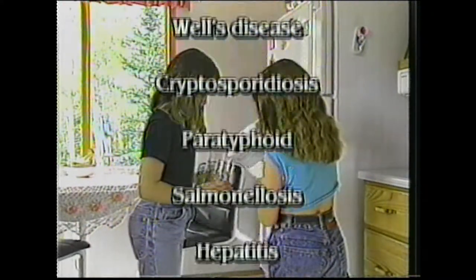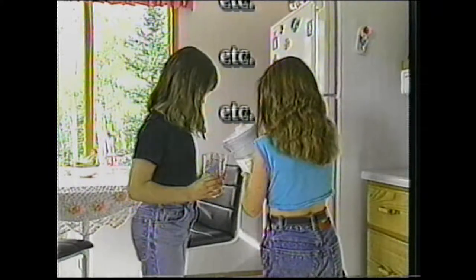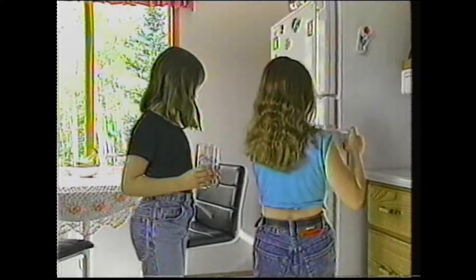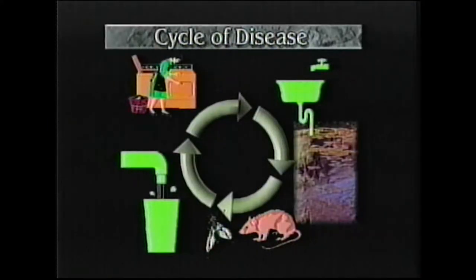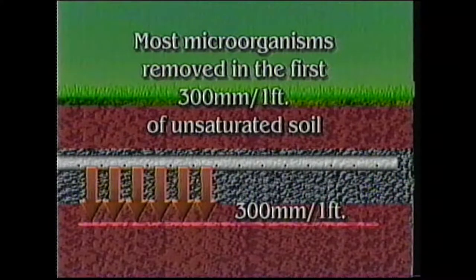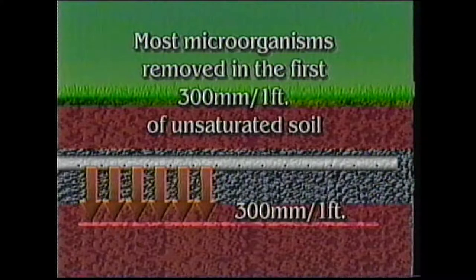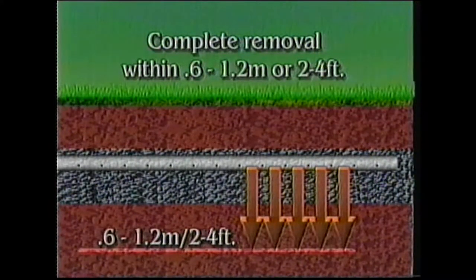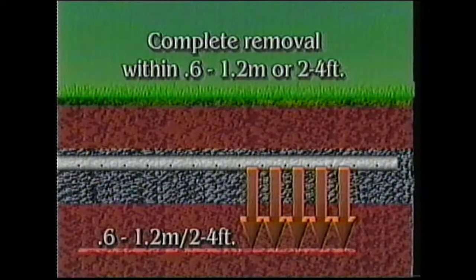The list is exhaustive and reads like a who's who of epidemics. Risks to human health arise through direct and indirect contact with sewage. The cycle of disease represents how disease is spread, and also how it can be prevented. In-ground systems break this cycle by removing most of the disease-causing microorganisms in the first 300 millimeters or one foot of unsaturated soil, with almost complete removal accomplished within 0.6 to 1.2 meters, or two to four feet from the soil absorption system bottom. This is a vital step in the process which protects groundwater.